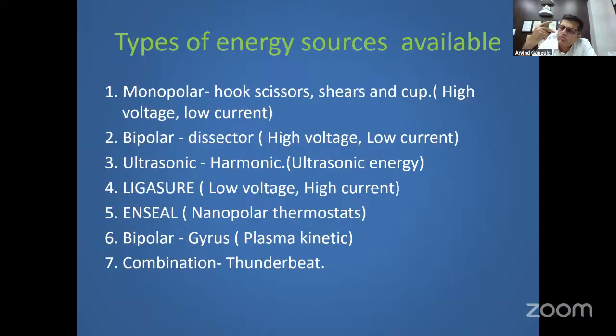So whenever you are using a harmonic, many times if you are going to use it around the hilum, you have to be very careful because the jaws will remain heated up for quite some time, which is not an issue with Ligasure. Ligasure is marketed by Covidien. Ligasure has got an insulation over its Maryland jaws, which helps in preventing lateral dissipation of the current. The monopolar hook is very commonly used as you go along near the hilum, and it is particularly used for fine and precise dissection.